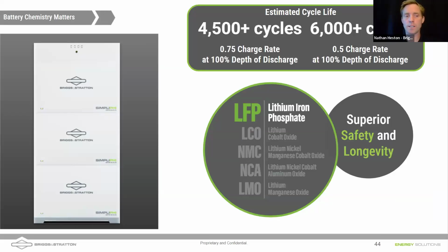We're going to highlight a little bit the 6.6 stackable battery that we have. One of the things that we really like about this battery is how quickly it installs, but it also has some pretty great performing specs. The battery can be discharged to 100% depth of discharge. It can be discharged and charged quite quickly. It can be charged at a 0.75 charge rate. So the C rate here is 0.75. And that means in an hour and 20 minutes, we can charge this battery from 0% up to 100%. So fast ratings on that.